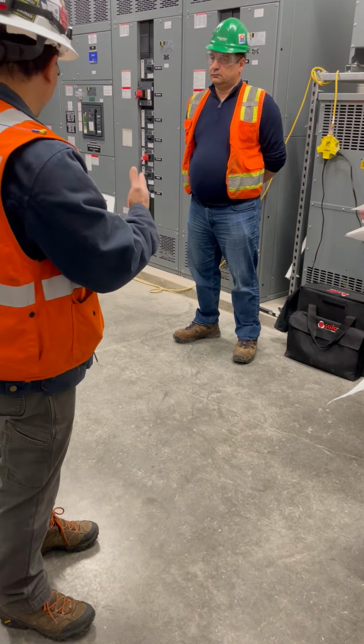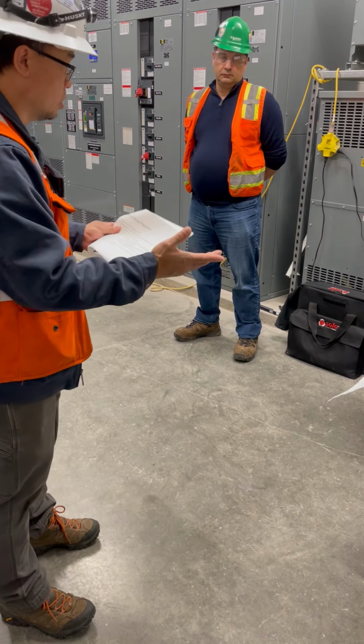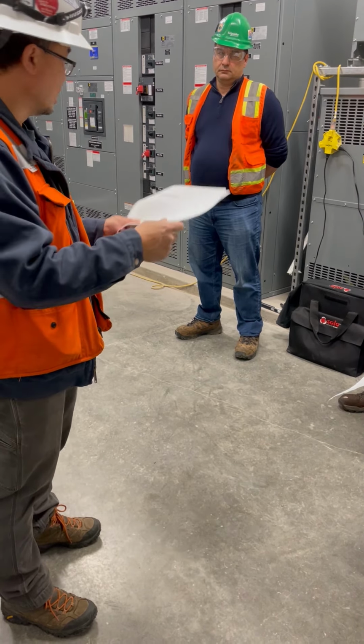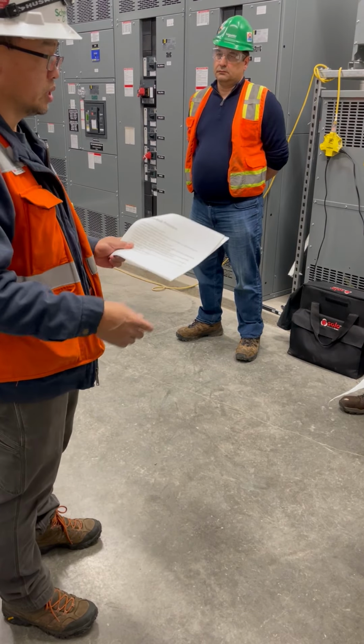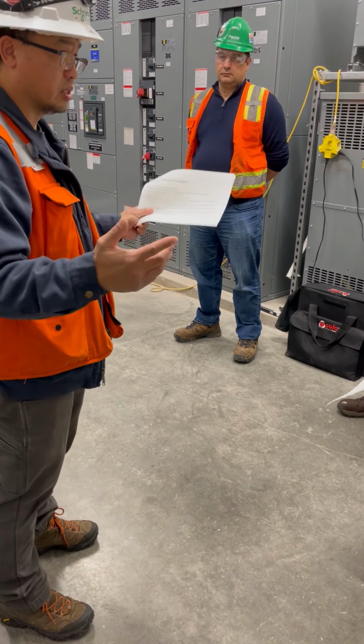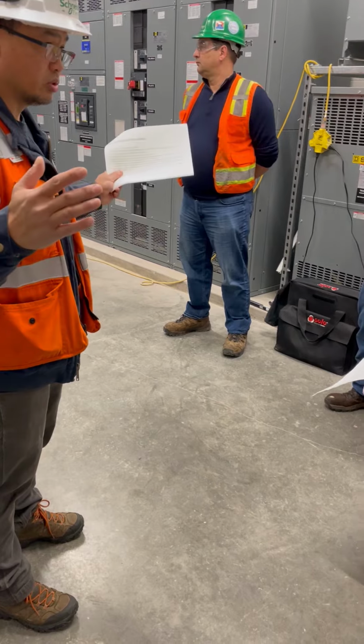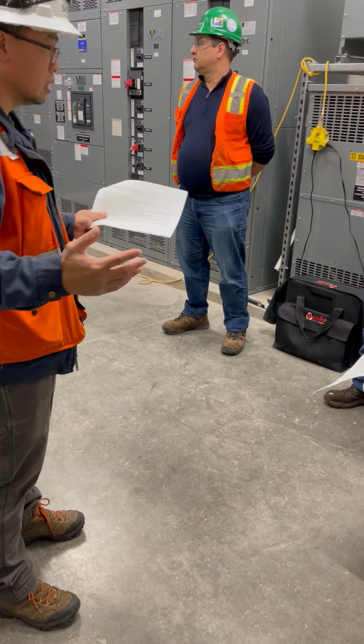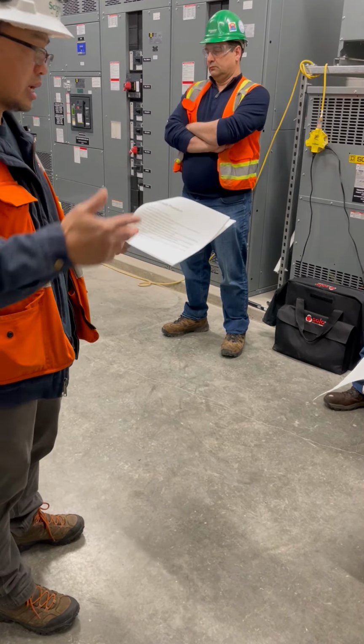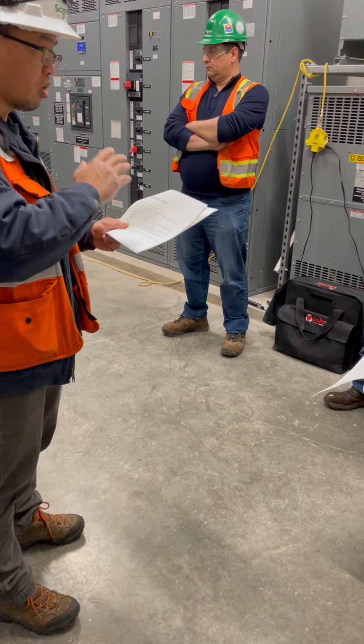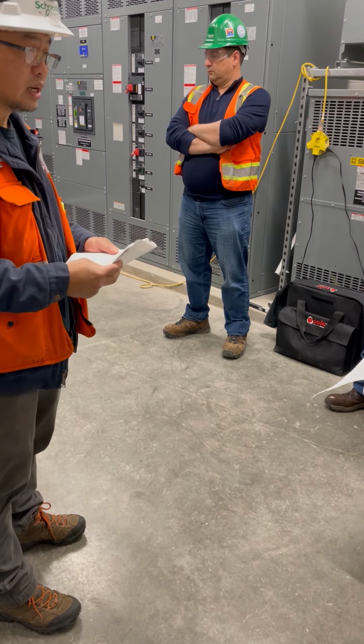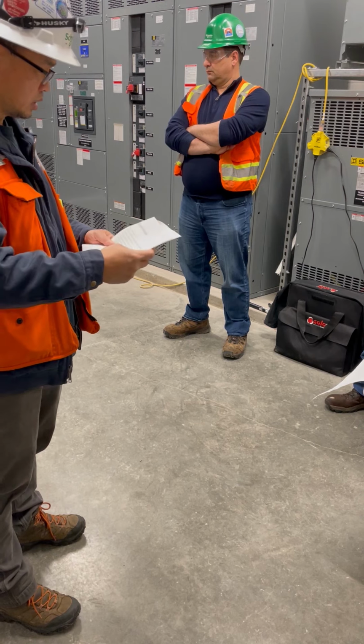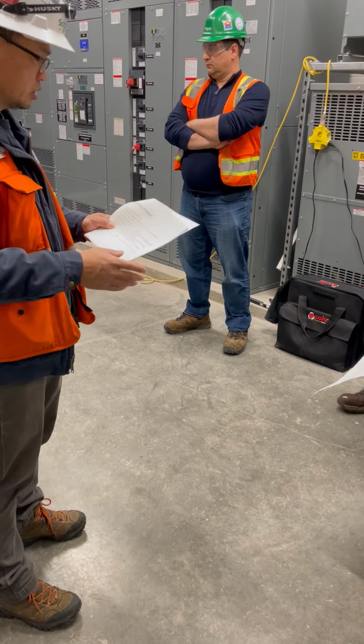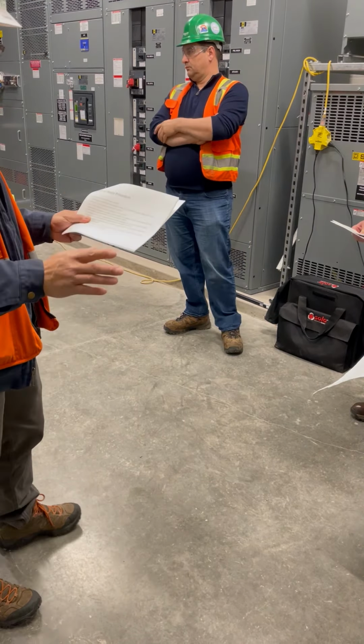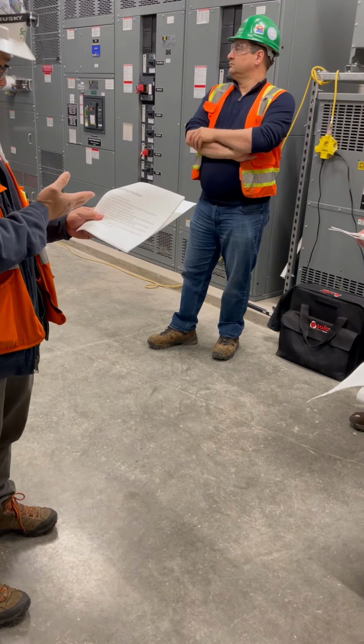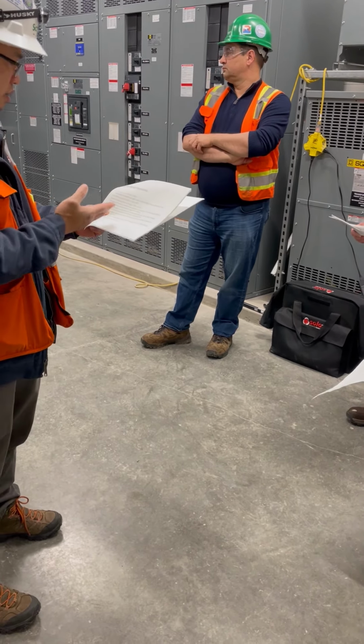So the first thing we always do to get these labeled is we need to develop a system model of the electrical system. Since this is a brand new facility, a consultant designed it, had a one-line developed, called out cable sizes and breakers. So we gather all that information and put it into a model, and we calculate the short circuit, coordination and arc flash.